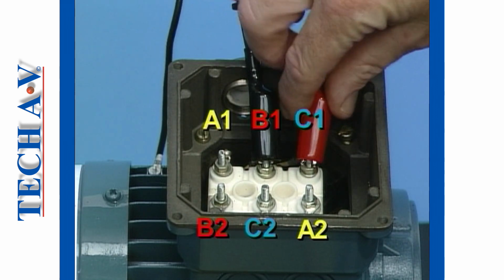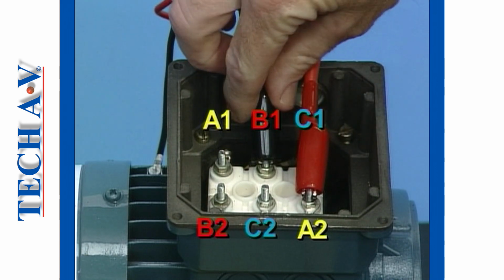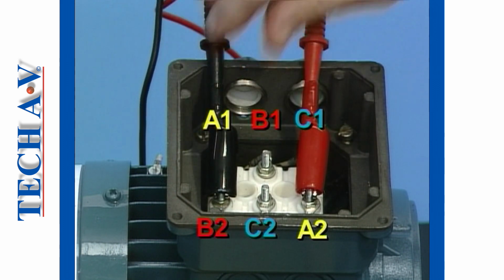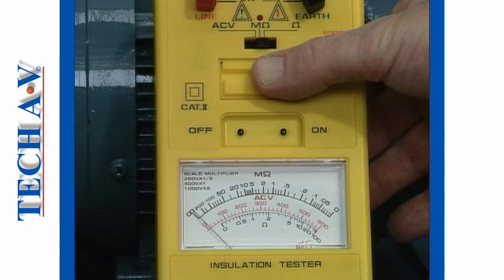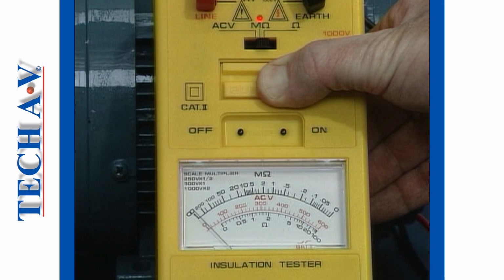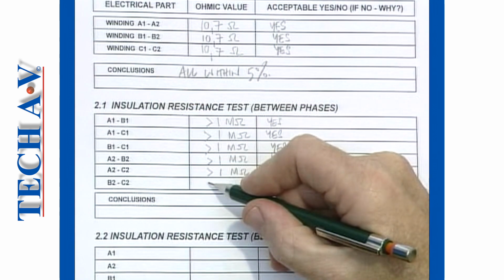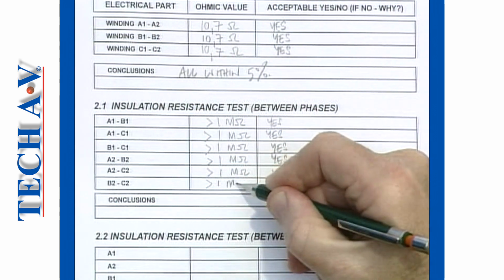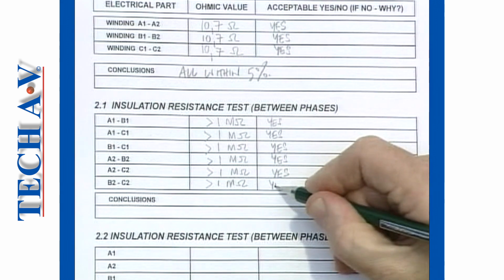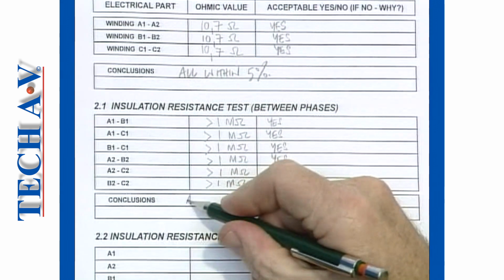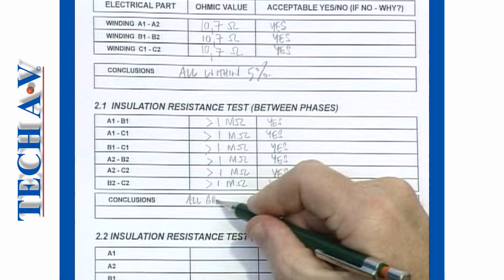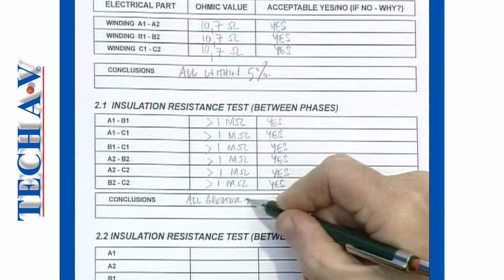Now connect one of the test leads to A2 and the other lead to B2. Test the insulation resistance once again, using the same procedures until the insulation resistance between all 3 windings has been measured. Record the resistance readings and conclusions on the checklist after each measurement is taken.